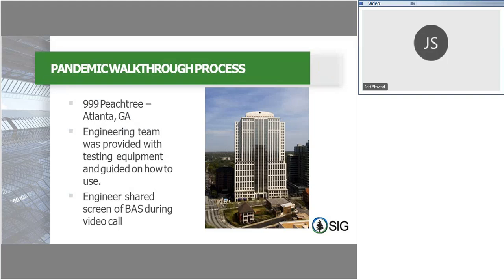For this property in particular, similar to Regents Plaza, we had a few terminal units showing unusual temperature readings, and SIG asked the engineering staff to take physical measurements in those rooms to verify whether it was an issue with the HVAC equipment itself or a calibration issue of the sensor. For all the issues we found, it was just sensor calibration. We worked with the team and their controls vendor to get the sensors recalibrated, then took measurements again and verified against the building automation system screen to show the readings were back within normal ranges.